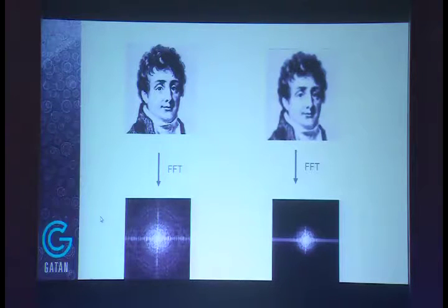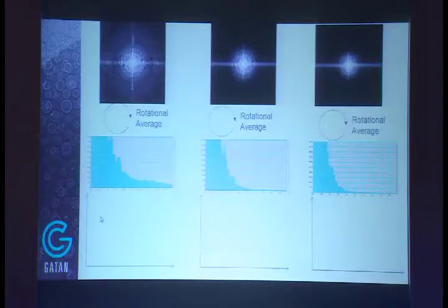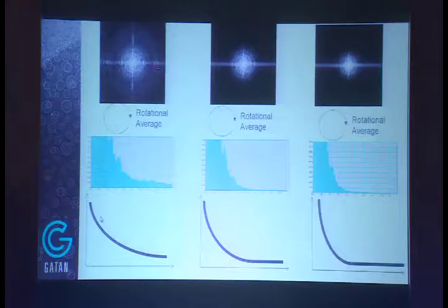When we're looking at DQE curves, what we do is take an image like this. Okay, this is the way to think about DQE curves. This is not actually the way DQE is calculated, but we take a Fourier transform of an image, and if you look at its rotational average from the origin to the edge of the image, you can see a plot that looks something like this. If we think about the signal to noise at each frequency, that roughly corresponds to the peaks of that plot. If you look at the signal-to-noise ratio at each frequency component, that's actually what DQE is.